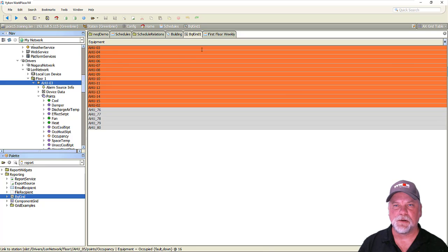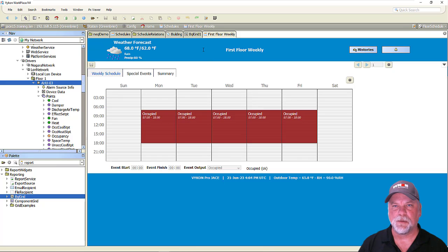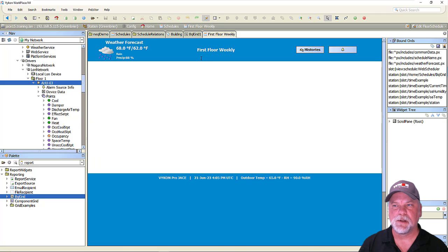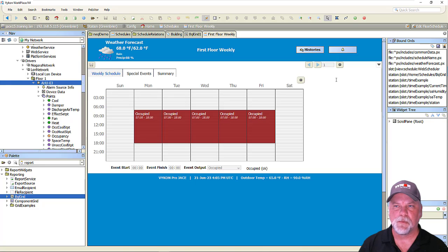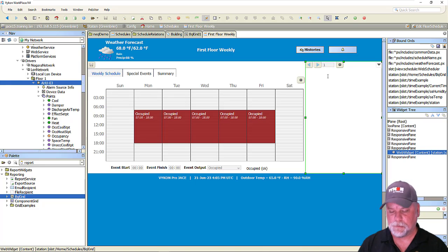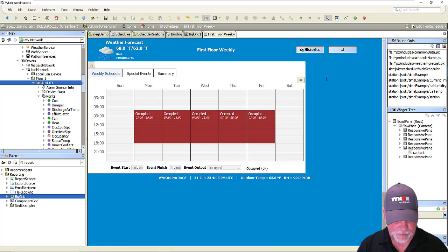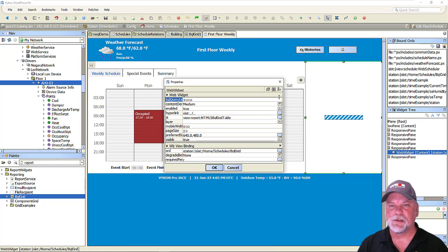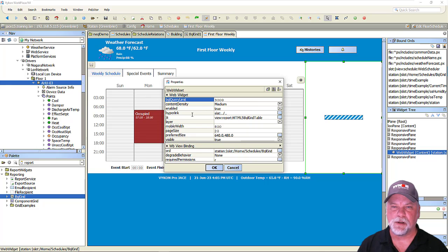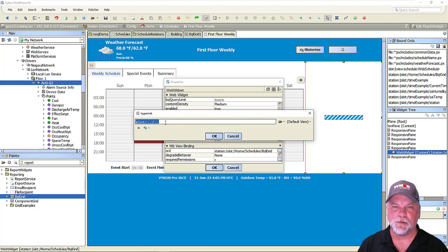Okay. So the idea, though, is with those component grids, what we can do is we can embed the component grid into a graphic. And I'll just delete. Oh, I guess I didn't need to delete that one out, but I'll just show you this one. It's actually a different BQL grid that's in there, but when you look at a BQL grid that you've embedded, it has a hyperlink property here. And this hyperlink is a relative hyperlink that defaults to slot colon. So in this case, I set up a relative backup hyperlink.